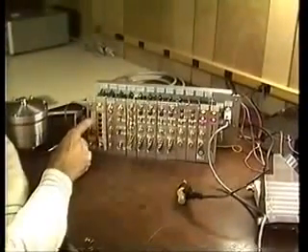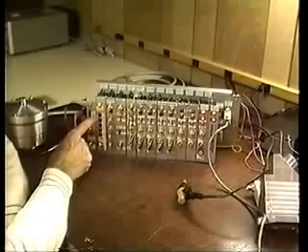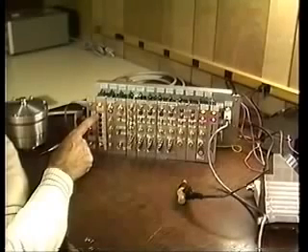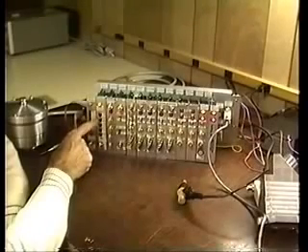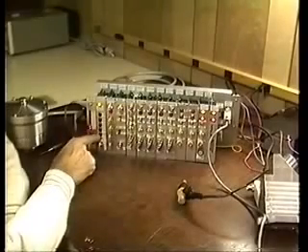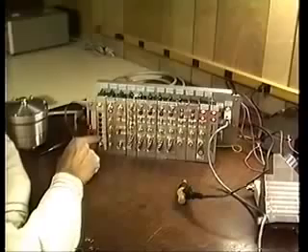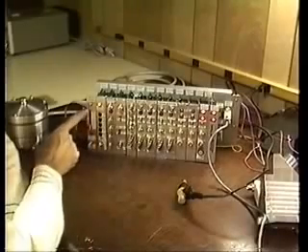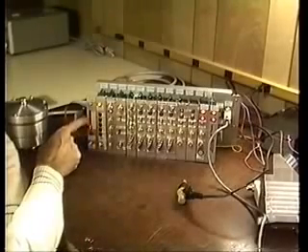alarm module. This module will give us an overspeed trip if the tach goes too high, if we have high pressure, low oil, or high temperature. In some cases we put a jar switch on there so that, like the Indy 500, that is a requirement. This module here is our tachometer module.